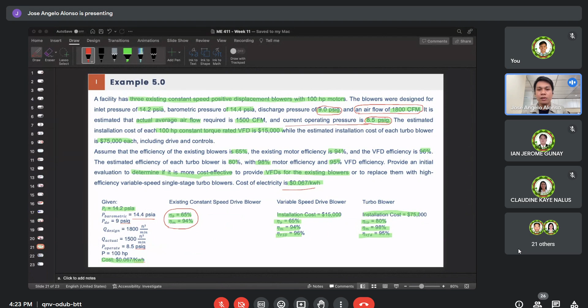Once we determine the blower power, or the power imparted by the blower to the fluid, we can then get its power consumption. We determine the power consumption by dividing that blower power by the blower efficiency and the motor efficiency.